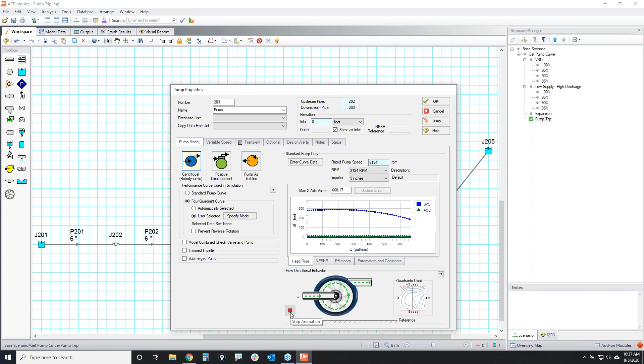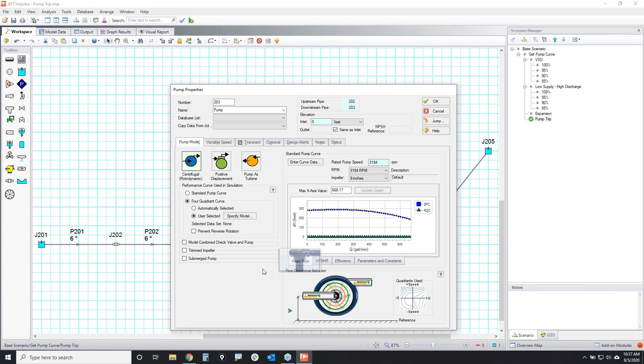Well, that's what a 4-quadrant curve is for. A 4-quadrant curve is a bit of a pump curve that is not designed to operate in all 4 quadrants. It's test data where pumps were intentionally operated in all 4 quadrants. So this is the normal pump curve area that you have, where you have positive flow and positive speed. That's your standard pump curve.